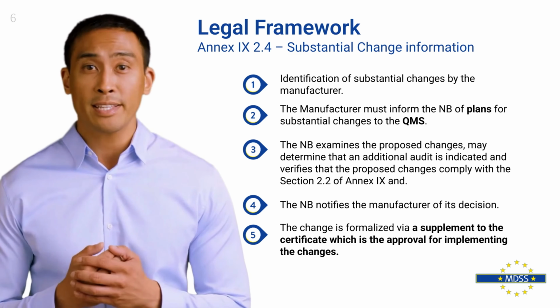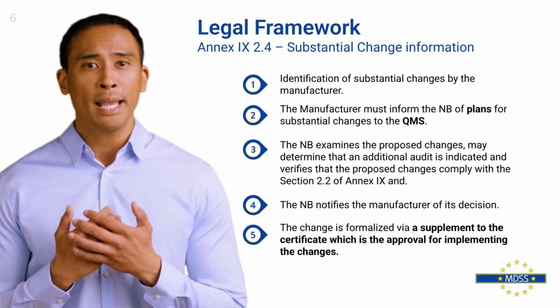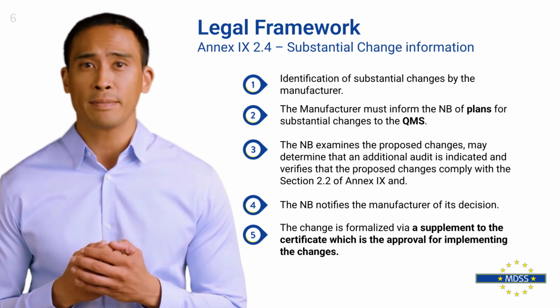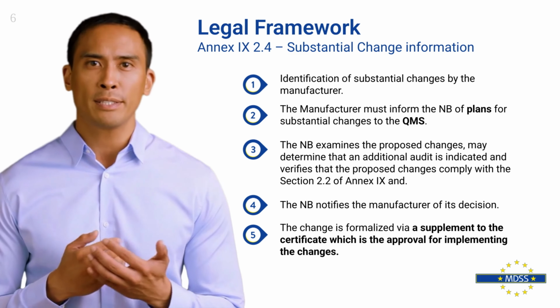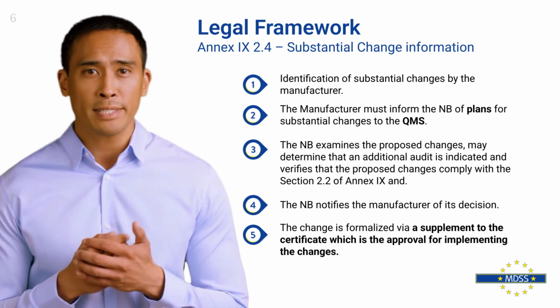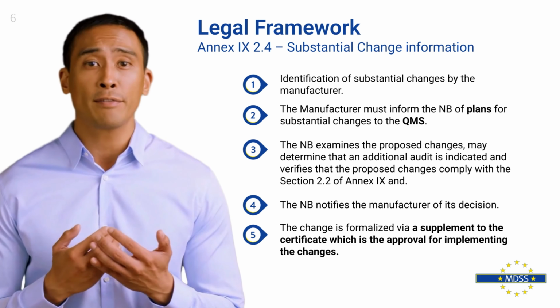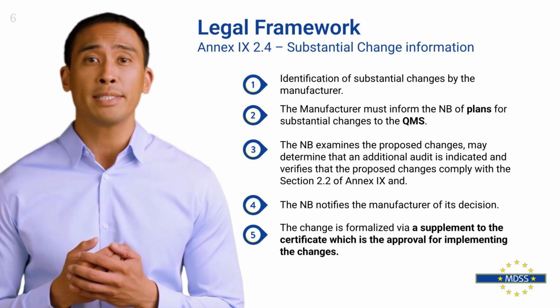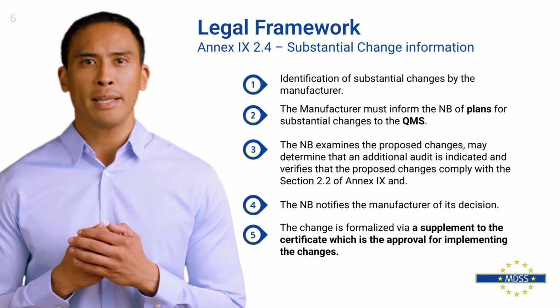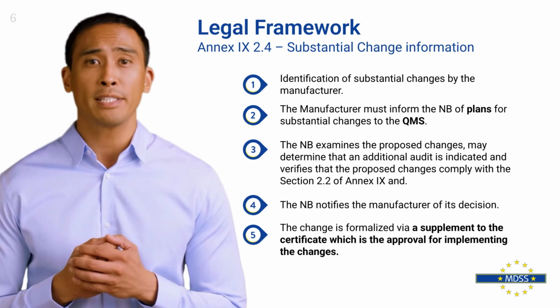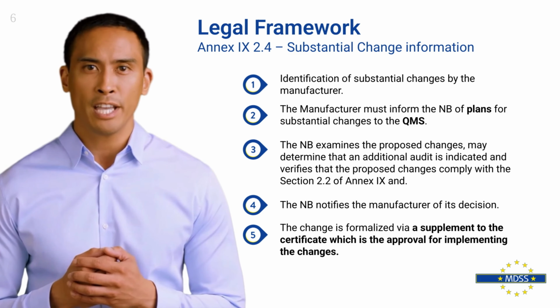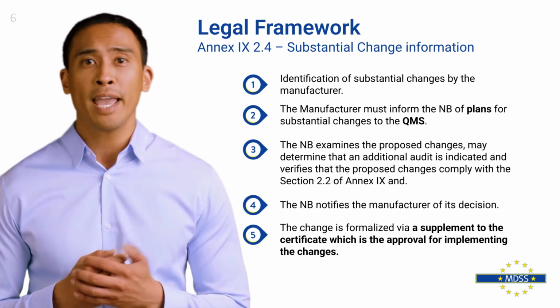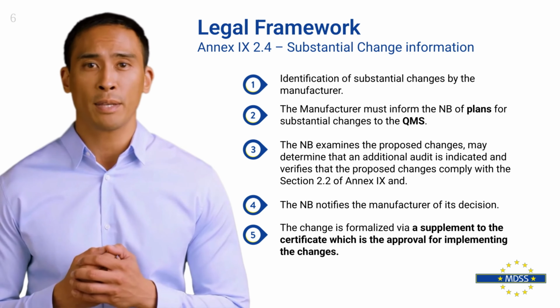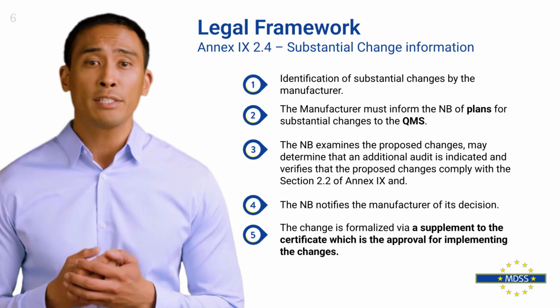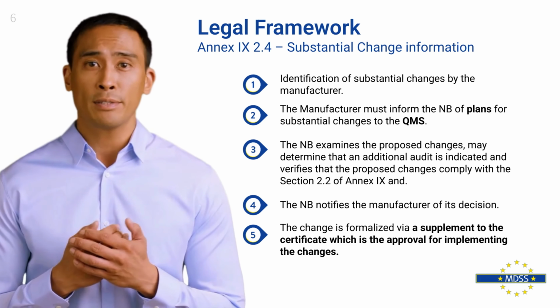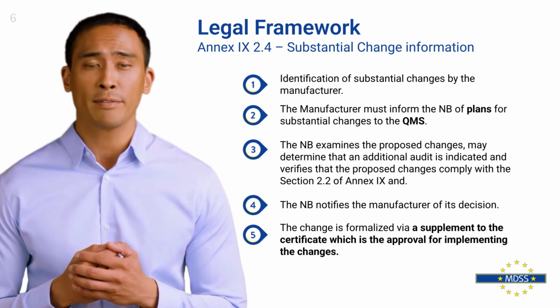The deeper one examines the wording of Annex 9, the more evident it becomes that it does not simply impose an obligation, it describes a process, identification of substantial changes. The manufacturer identifies via its quality management system future changes and checks whether those changes are substantially affecting the quality management system. If the changes are substantial, then the manufacturer informs the notified body of plans for substantial changes. The notified body shall assess the proposed changes and determine whether additional audits are needed. The notified body verifies that the quality management system still complies with Section 2.2 with those proposed changes implemented. The notified body shall inform the manufacturer of its decision, including assessment results and, if applicable, audit conclusions. The notified body must provide a supplement to the certificate if the changes comply with the requirements. This structure underlines that compliance in this area is about integrating a decision-making process into the manufacturer's quality management system, a defined part of the conformity assessment itself.